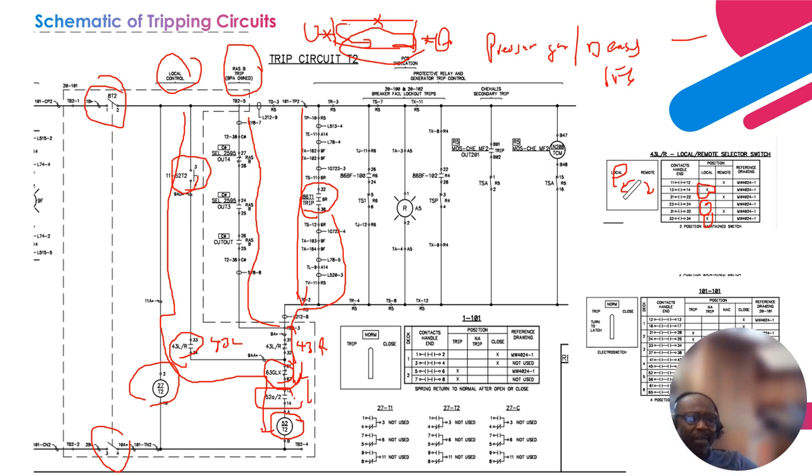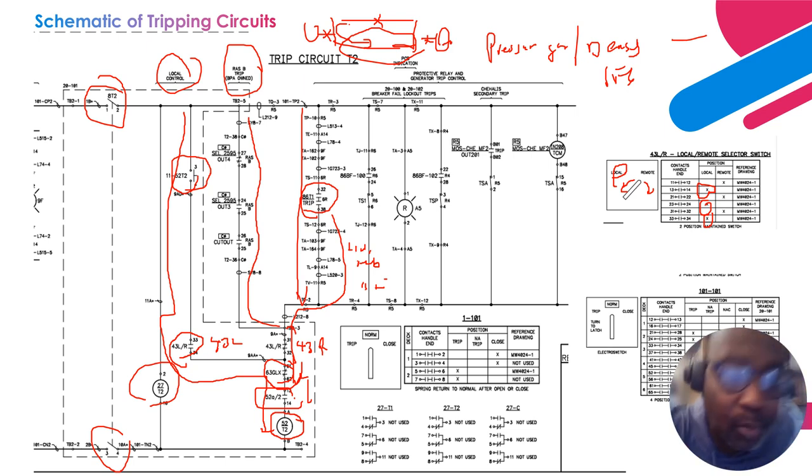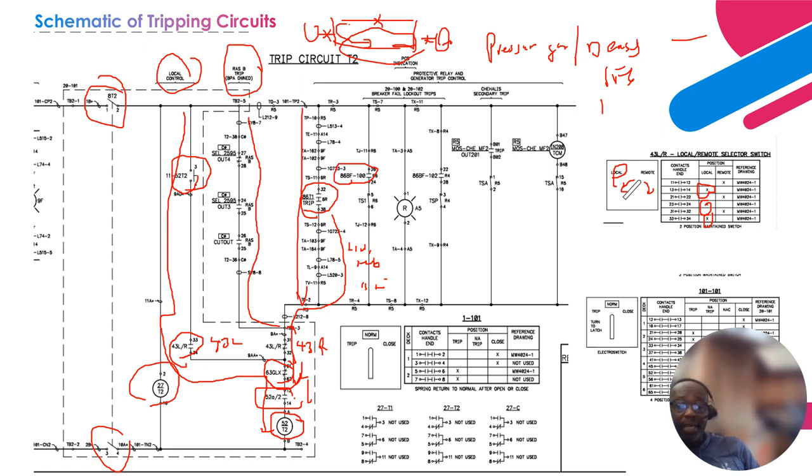Remember, I made mention that the 86 BF is a lockout relay for the breaker failure. BF means breaker failure. So when does the breaker failure come in? It comes in when the trip circuit for this breaker fails. Let's say if trip coil one fails, then that is when the lockout relay for the breaker failure gets energized, and that is supposed to provide a permissive input to this path to be able to energize this trip coil.